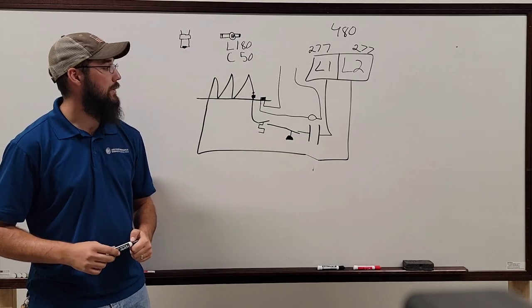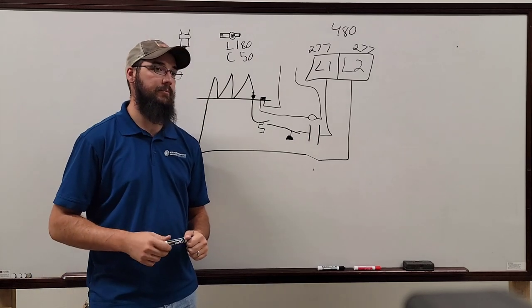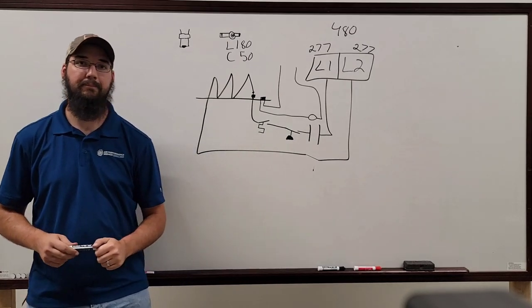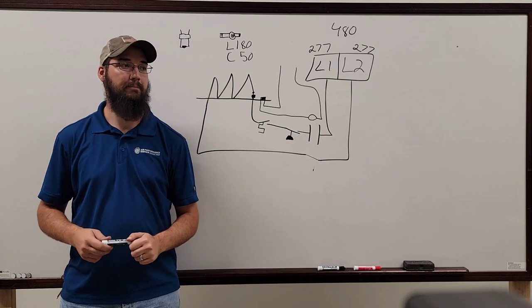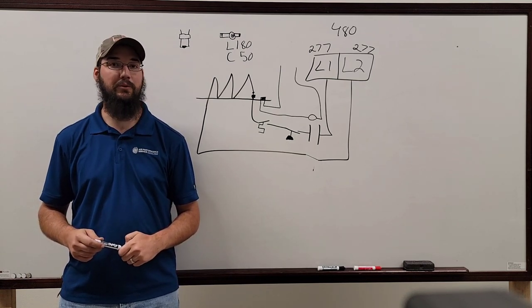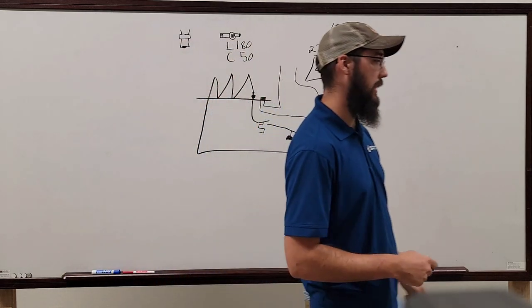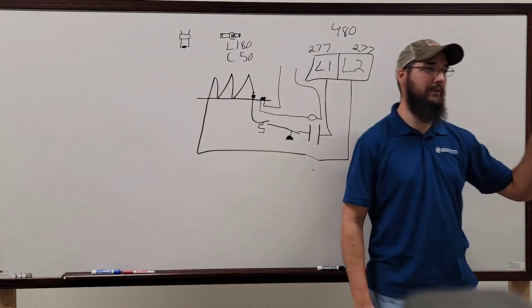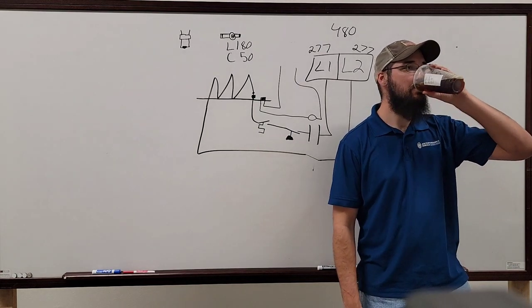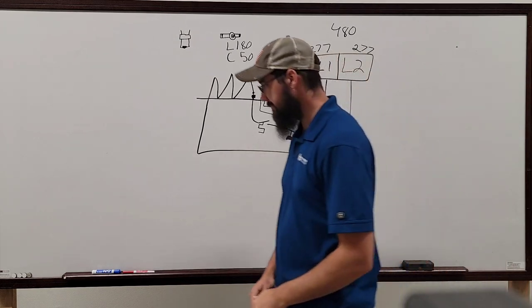So how do we determine how many BTUs we're producing on the heater? Anybody know? It's refresher class. We're going back into this. Time to start thinking about this stuff. So it's volts times amps, and that's equal to watts. Watts times 3.414 is your BTU.